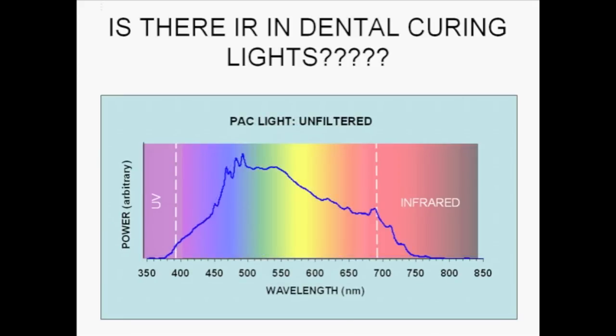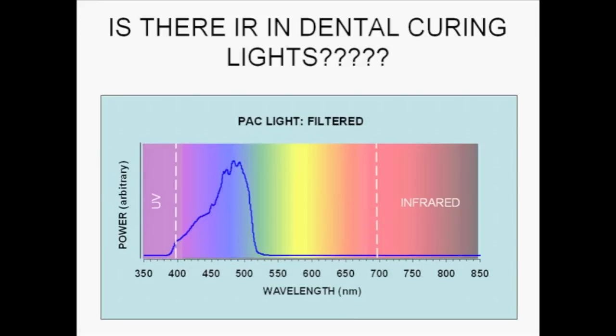The spectral emission of a plasma arc unit, the so-called PAC light, also indicates very broad emission over this range. However, when the unit is properly filtered, its light output is again restricted to only that within the short visible spectral range, blue and violet.